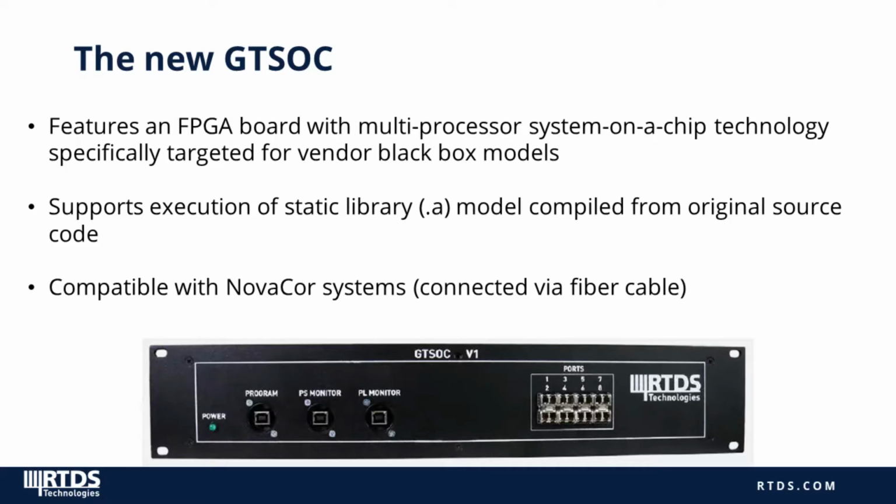The GTSOC supports execution of static library .A models, which are compiled from the original vendor control source code. And it's compatible with NovaCor systems only. It's connected to the NovaCor chassis via fiber cable. So unfortunately, the GTSOC is not compatible with PB5 or prior RTDS systems.